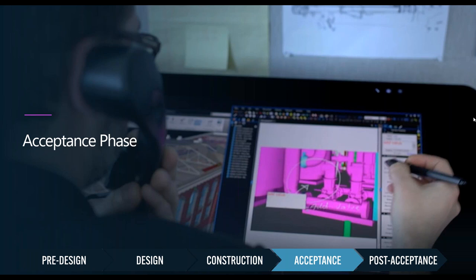So after we move into construction, we then move into the acceptance phase. Now, the acceptance phase is where we functionally test all the equipment, where we walk through every component of the sequence of operations, every component of how equipment is supposed to operate, and test it to ensure that it's going to operate the way it is intended.